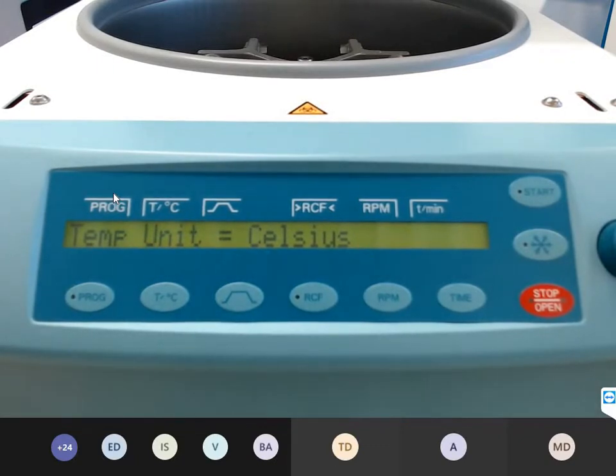You can change the temperature unit in Celsius and Fahrenheit, the ramp unit. We can change the ramp unit in time or in steps. Steps means 0 to 9. 9 is the highest and the fastest brake and start. Or you can say start or set 5,000 RPM and reach the 5,000 RPM, for example, in 10 minutes. It's also possible.